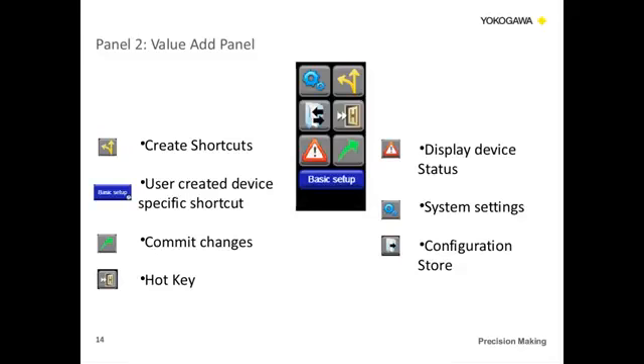An example is if I'm connected to a Yokogawa EJX pressure transmitter, the shortcut keys I set up for that transmitter are only going to show when I hook to that transmitter. If I connect to a flow meter instead, I'm not going to see all those same shortcuts, and that's what was being talked about.